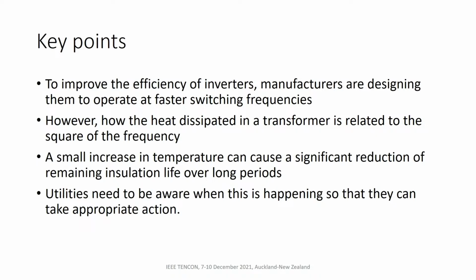So we were looking at this, and we thought, okay, if we can dissipate more heat within the transformer, so it's heating up, well, the life remaining of the transformer is a function of its temperature. If you only need to go up maybe 6 degrees, then you've halved the remaining life of the transformer. Usually, a transformer is designed and rated to last quite a long time, so you get an inflection point. If you're looking at maybe a 6 degree increase at the lower loads, then it's probably not going to do that much, because the life remaining will be fixed by maybe corrosion of the tank or other things happening around it. But if somebody is running the transformer at a very high load, and then we have another 6 degrees, say, of harmonics, then we've halved the life remaining. So it can be significant.